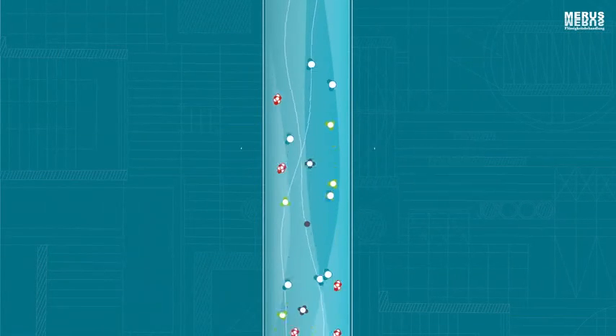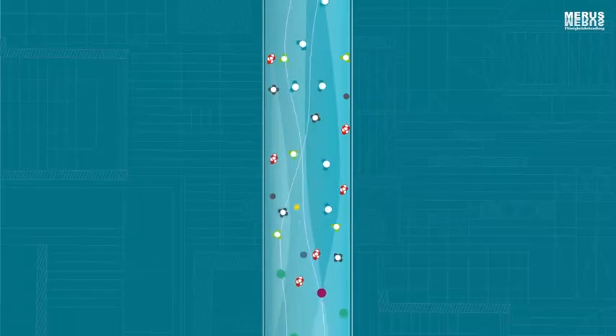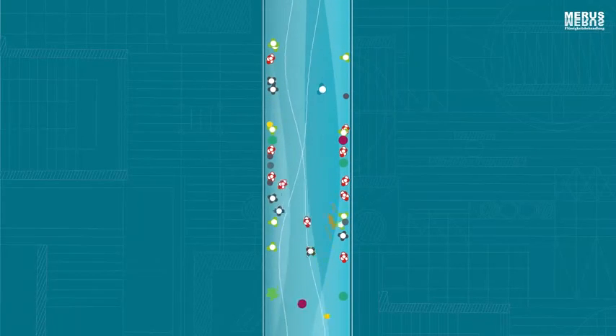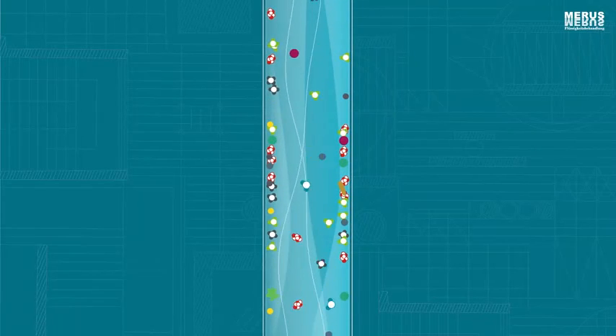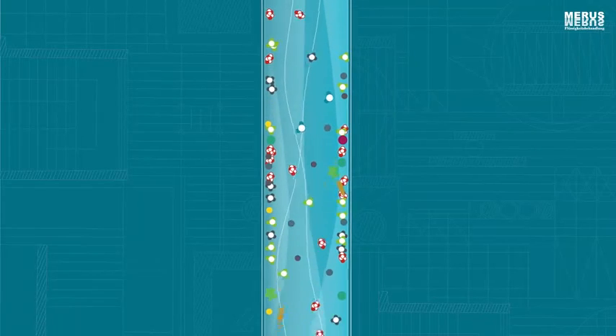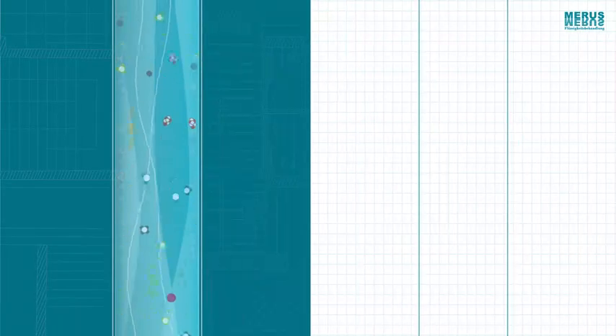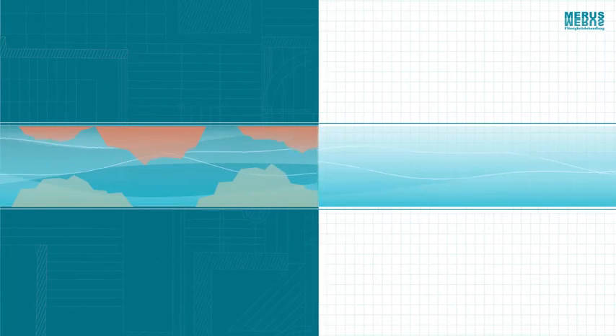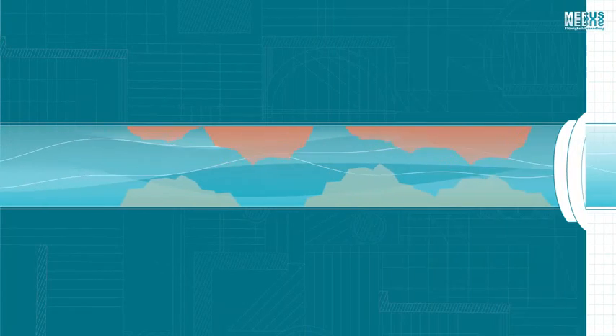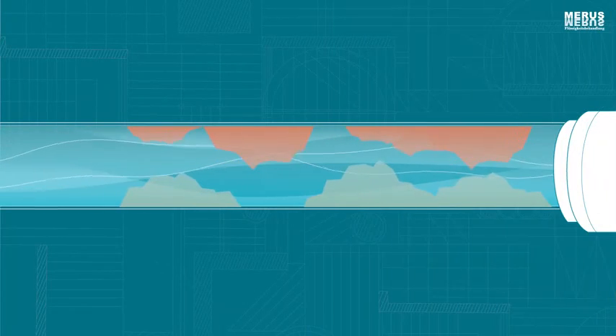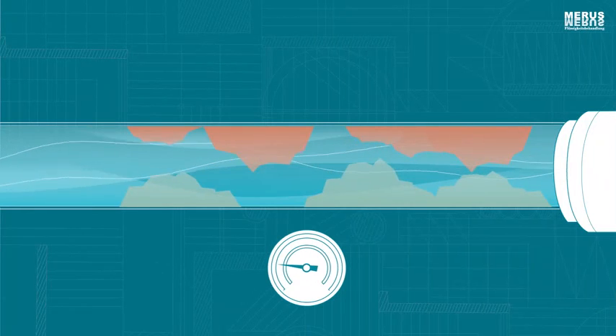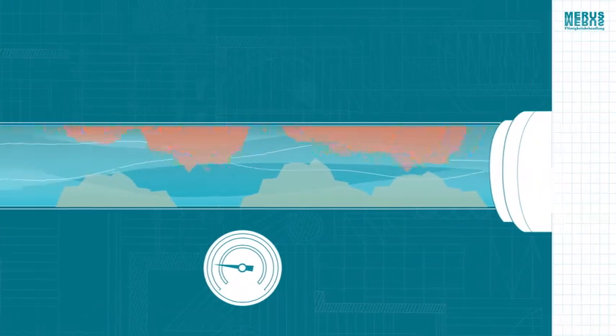With increasing deposits of limescale and other foreign substances, the friction is even higher than on clean pipes. In addition, the pipe's diameter is decreased by the buildup of deposits. A smaller diameter reduces the pressure at the heat exchanger's outlet further.